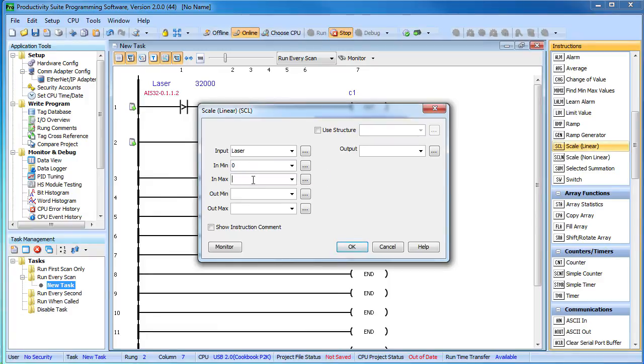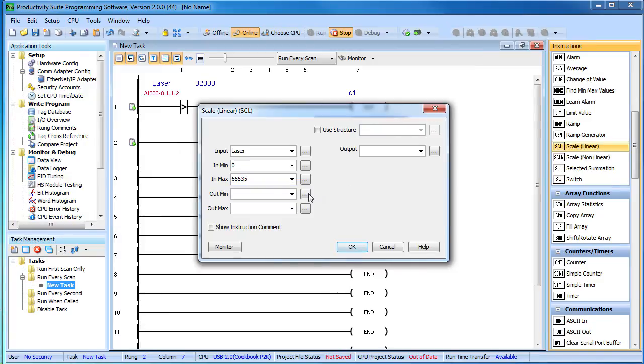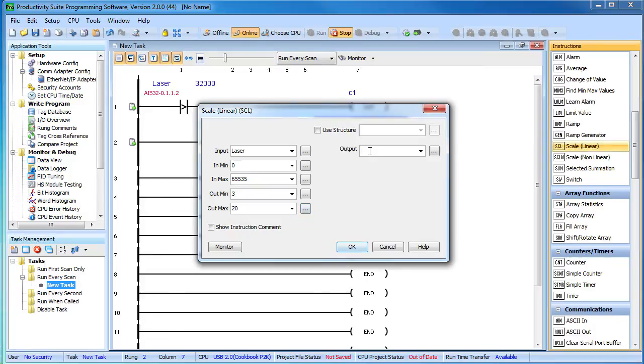The laser is 0 to 10 volts input, which to the PLC is 0 to 65535, and the sensor was set up to go from 3 to 20 inches over that range. Let's give the new scaled value a name, we'll call that laser inches.